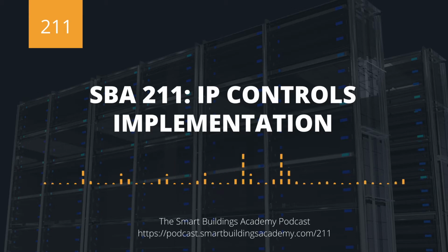Now, there still are quite a few manufacturers out there whose take on IP controls quite simply is to use a BACnet advanced controller template. If you're familiar with the advanced controller template, it has scheduling, it has trending, it has alarming built into it. But it's not got that full-blown supervisory with field trunk capacity on it.